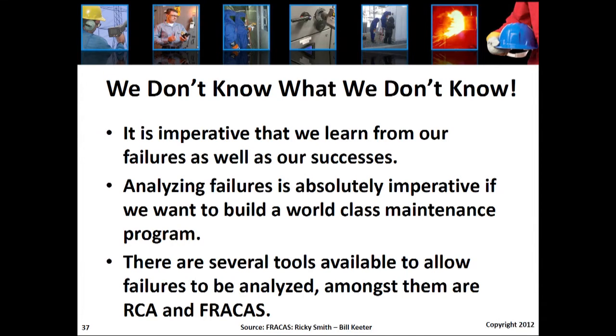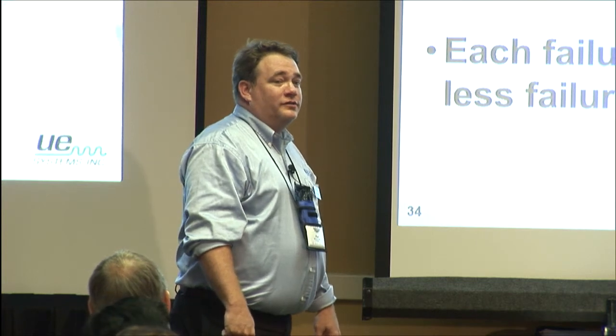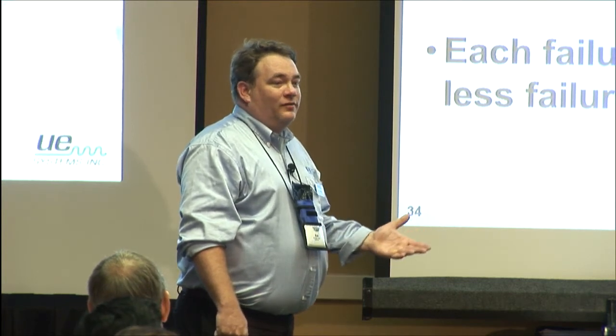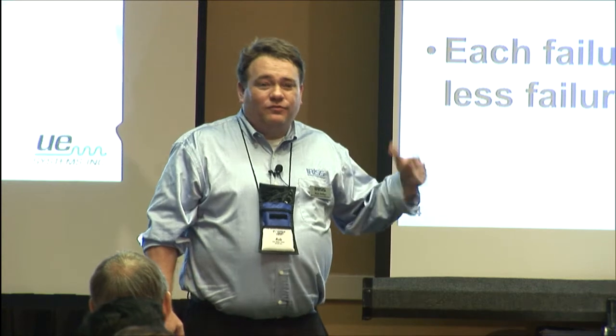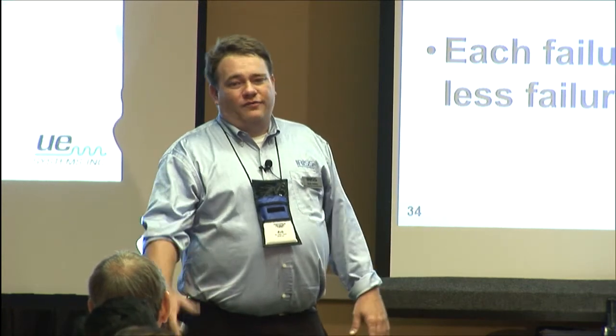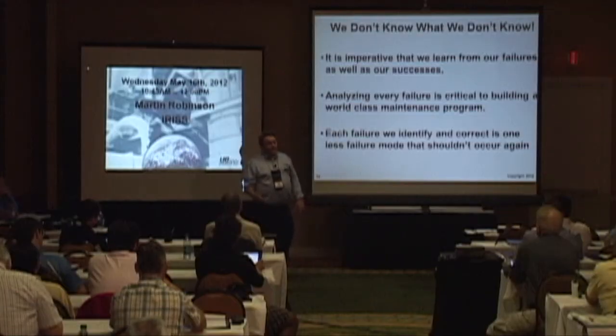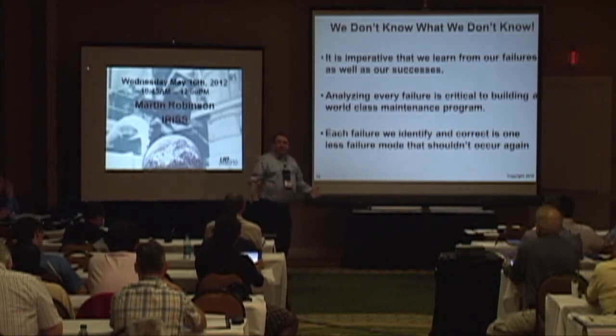So, when was the last time your breakers were relay tested? Well, I don't know. Analyzing every failure is critical to building world-class maintenance. Just because something fails doesn't mean we slap a new part on it and go on down the road. Figure out why it failed.